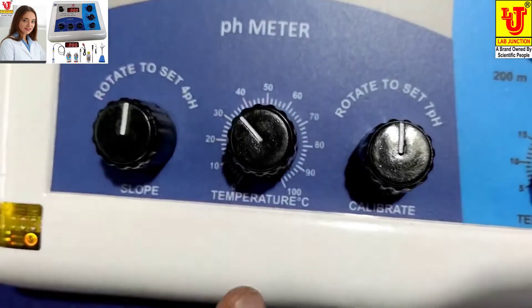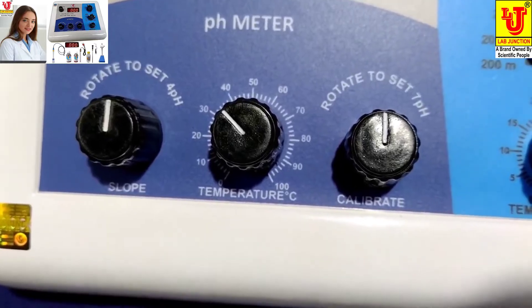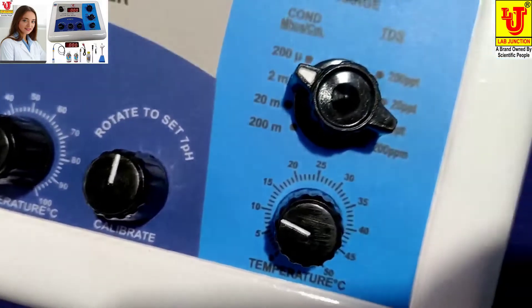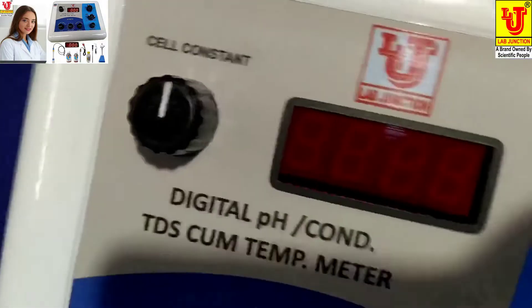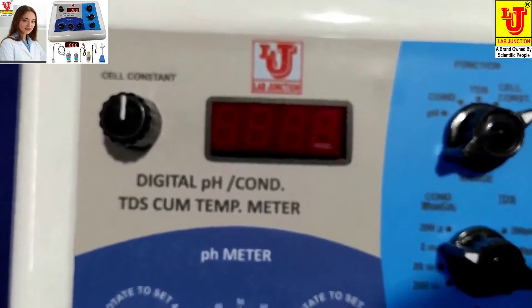These three knobs are for pH: one is 4 pH, one is temperature setting for pH, and one is 7 pH for calibration. This control is for cell constant — feeding cell constant for conductivity and TDS values.